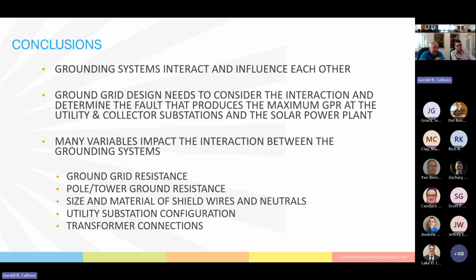So the ground grid design needs to consider the interaction and determine the fault that produces the maximum ground potential rise at the utility and collector substations and at the power plant. And it may not be when somebody says, okay, I want you to design the collector station, and they don't want you to consider the fact that there's a utility sitting right next to it, 20 feet away, how that's going to impact it. And as you can see, there's a large impact of what the voltages are that are developed in the solar and in the collector station, just depending on how close the utility substation is to the collector substation. There's a lot of variables that can change this.